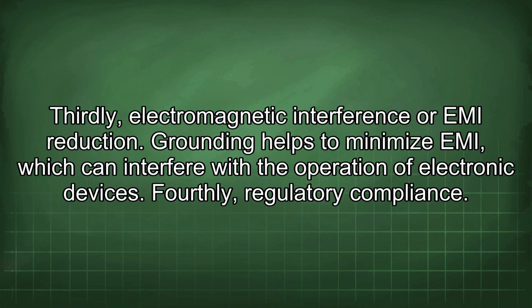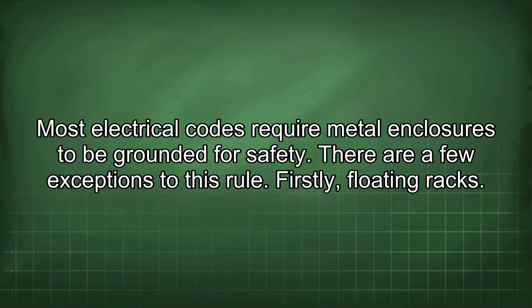Thirdly, electromagnetic interference or EMI reduction. Grounding helps to minimize EMI, which can interfere with the operation of electronic devices. Fourthly, regulatory compliance. Most electrical codes require metal enclosures to be grounded for safety. There are a few exceptions to this rule.